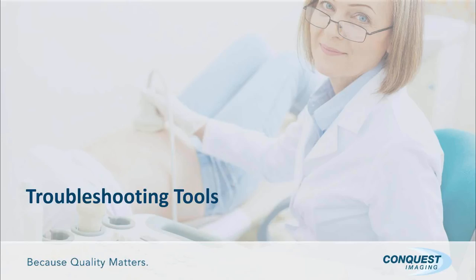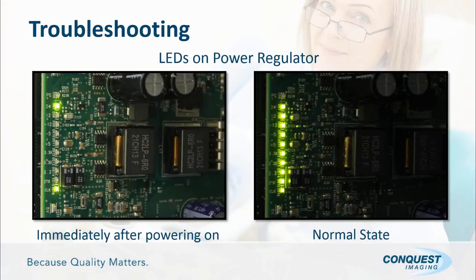Additional troubleshooting tools. We have the several sets of LEDs that I'm going to describe here. We have LEDs on the power regulator board. There are several different types of regulator boards. This is one that's fairly common. And as soon as you turn on the system, you'll see the image on the left. You'll get the 2 green lights. Some of them will also have the light just above the 24-volt one on top will also flash on. Not all of them do that.